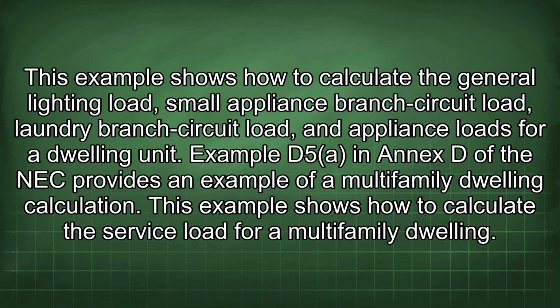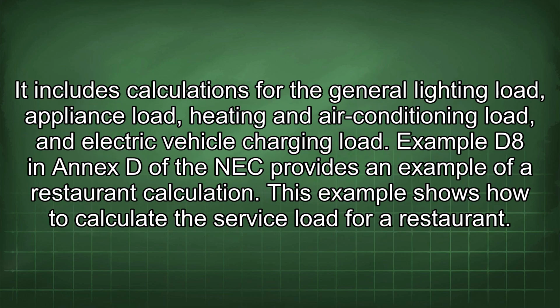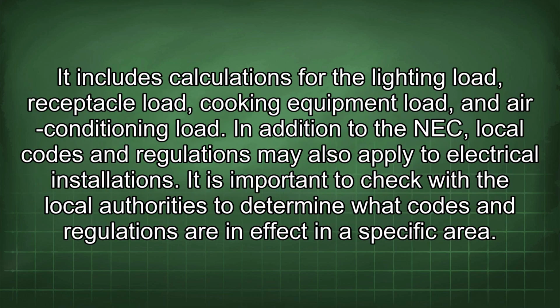Example D5(a) in Annex D of the NEC provides an example of a multifamily dwelling calculation. This example shows how to calculate the service load for a multifamily dwelling. It includes calculations for the general lighting load, appliance load, heating and air conditioning load, and electric vehicle charging load. Example D8 in Annex D of the NEC provides an example of a restaurant calculation. This example shows how to calculate the service load for a restaurant. It includes calculations for the lighting load, receptacle load, cooking equipment load, and air conditioning load.